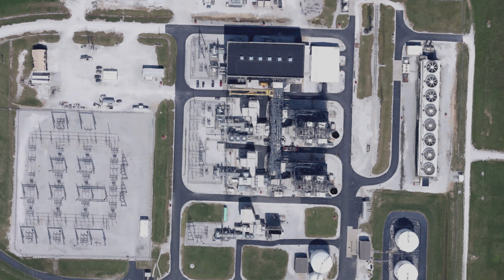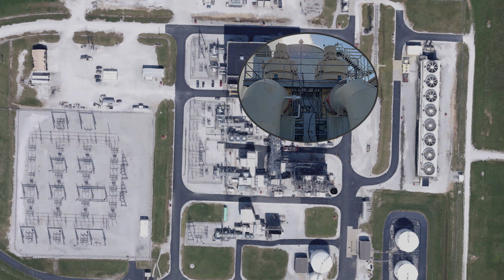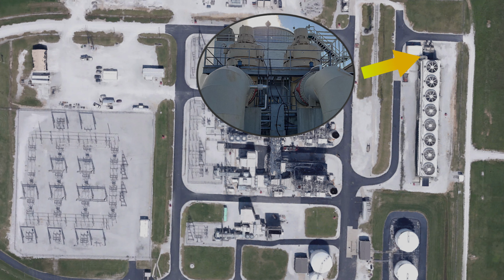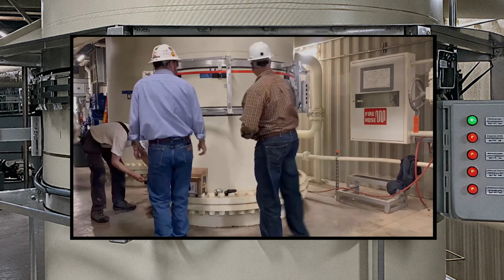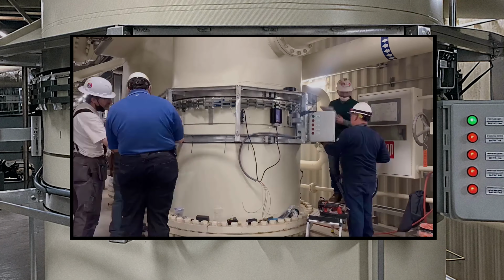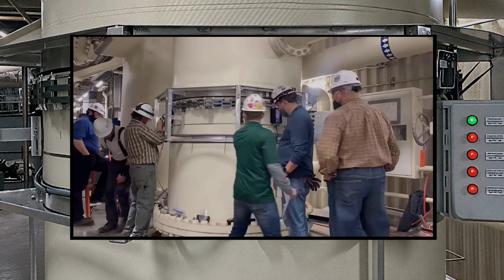A 500 megawatt combined cycle power plant in the U.S. Midwest was looking to reduce chemical and cooling water usage in their 8-cell cooling tower system. To achieve these goals, a custom 72-inch HydroFLOW unit was installed on the recirculating cooling system at the inlet to the condenser.